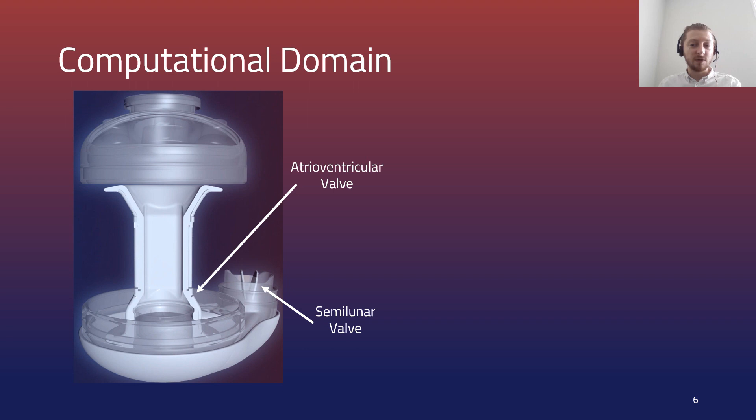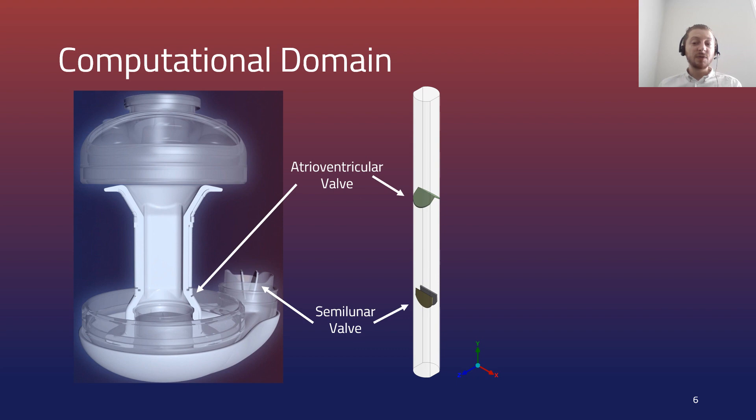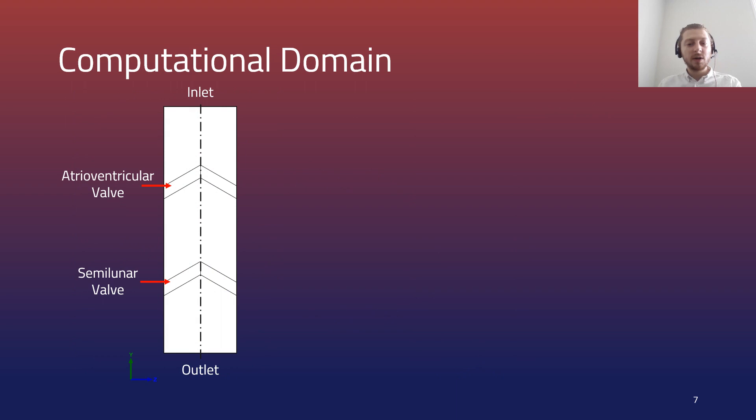To achieve this aim the project focused on the most essential aspect of the problem, the pair of bileaflet valves. The computational domain considered for this study was a simple fluid cylinder containing the two valves in series. This simple model allowed for faster development of the modeling strategy compared to if the full device had been considered initially. The domain was simplified into a quarter model using symmetry planes to decrease the computational cost.